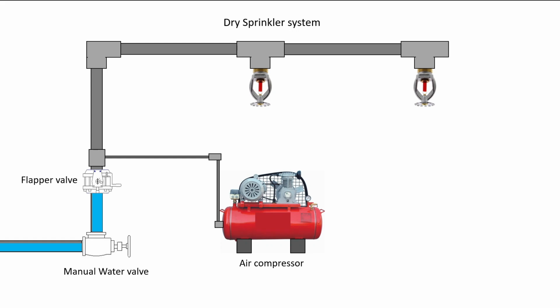Dry sprinkler systems operate in a different way, and the reason you would want to use a dry sprinkler system is in locations where it is cold. Sometimes sprinkler heads are required to be outside the building envelope. In those situations, standing water in sub-zero temperatures could cause the water to freeze and burst the pipe. Other times, we need to have pipes that go through environments that are extremely cold, like large walk-in or freezer warehouses where food distribution takes place. Again, these systems need to be dry because standing water will freeze and break the pipes.